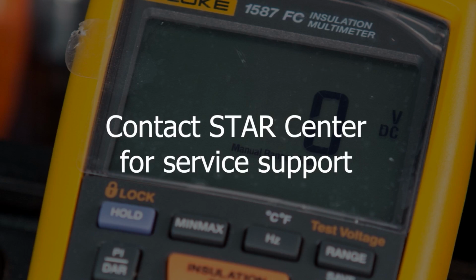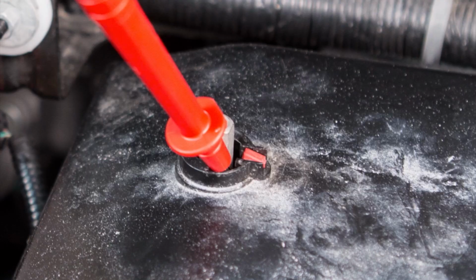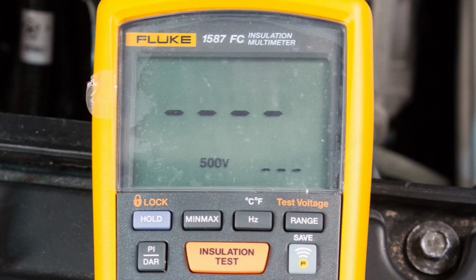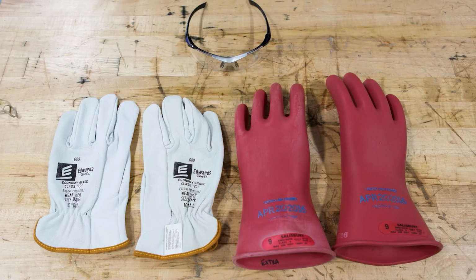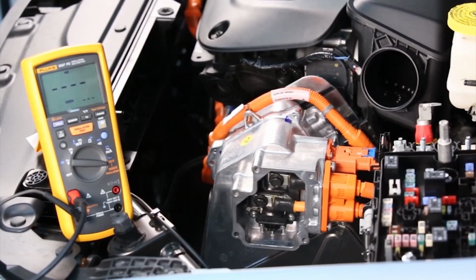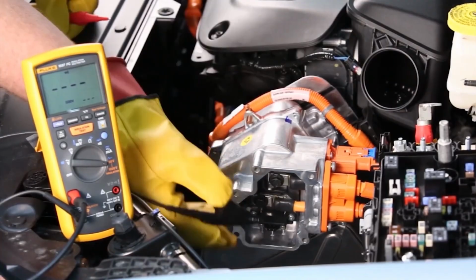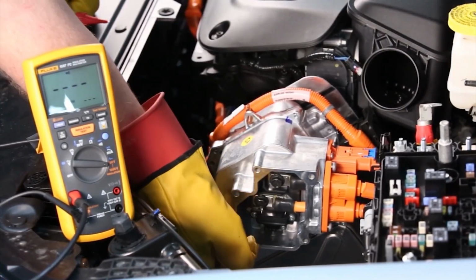Always observe these precautions prior to taking an isolation resistance measurement. Have known good test leads. Set the test voltage to 500 volts. Always wear HV gloves and safety glasses. Now we'll measure the isolation resistance at the power inverter module or PIM high voltage terminals.